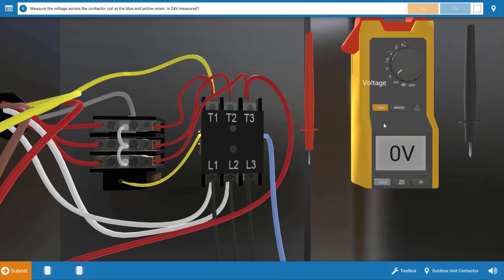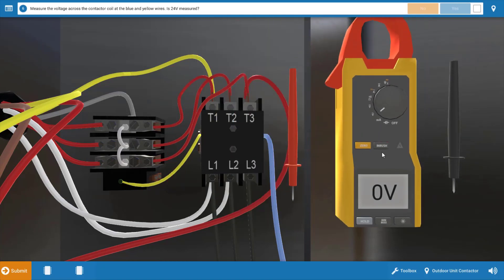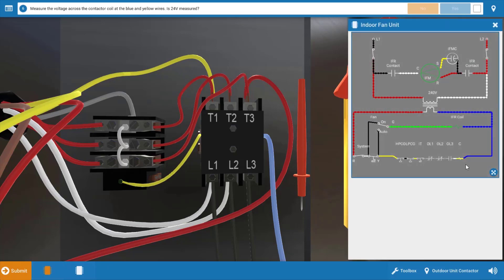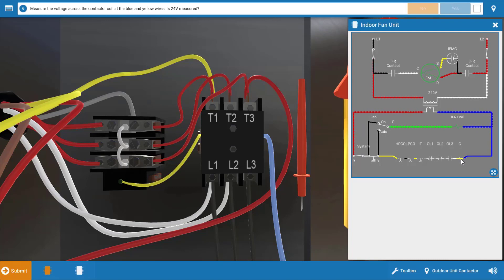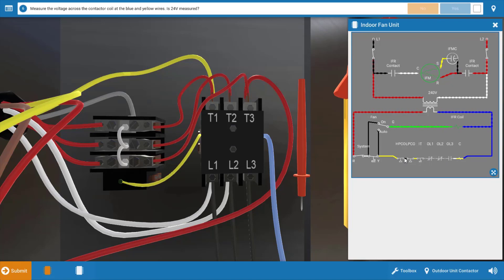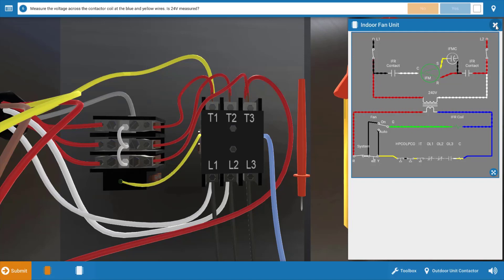What could cause this? Well, there's a whole lot of things that would turn these two motors off, but let's take a look at the diagram again. Our contactor coil could be the fault here. It's possible without this coil intact that the contacts do not close and it doesn't turn on the condenser fan motor and the compressor. But it's also possible that any of these preceding switches, these safety switches here, the three overloads, the internal thermostat, the low pressure and high pressure cutout, as well as the thermostat could be open, breaking power to that contactor coil. So we're going to investigate each of those.